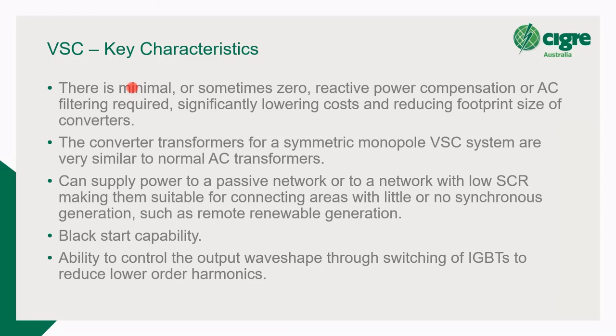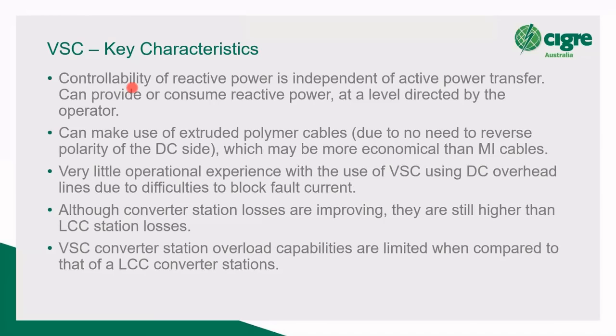The converter transformers, if you've got it in a symmetric monopole configuration, are very similar to normal AC transformers. They can supply a passive network if you design them correctly. They have a black start capability if you've designed and specified it correctly. And you can do some pretty neat things with the output. You have such control over the converter that you may be able to use VSC converters, for example, to help you with an existing harmonic problem at the same time if you needed to.